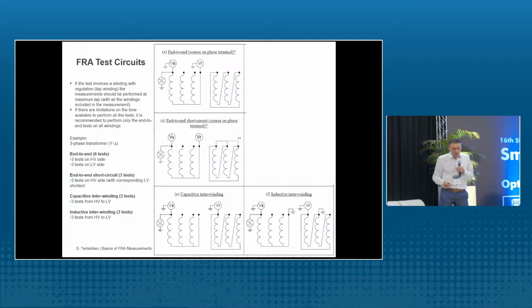There are different ways to apply the voltage to the windings. You can apply it to the high voltage winding or to the low voltage winding. You can short circuit the secondary, or you can leave it open. You can measure the response voltage also on the other voltage level. So there are different setups. This is described in a standard, which setups are possible. I do not want to go too much into the details of these connections.